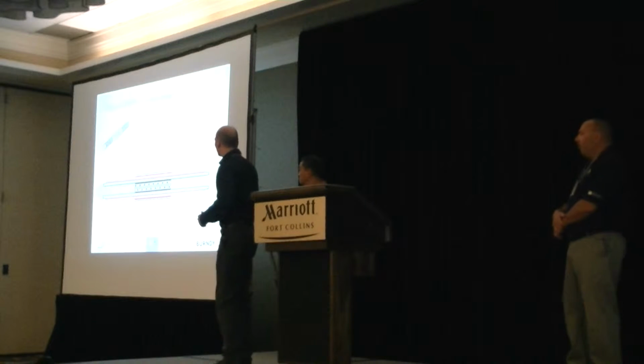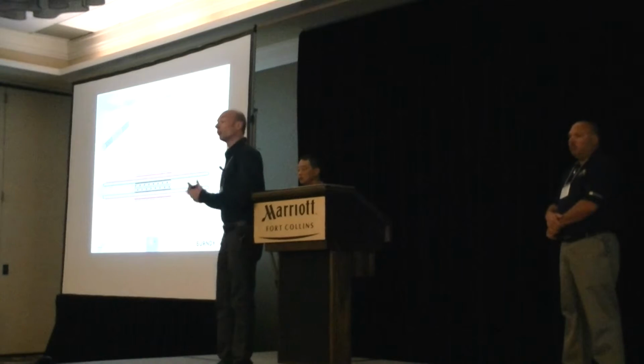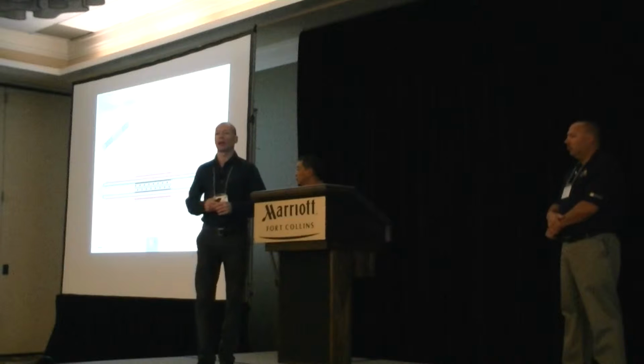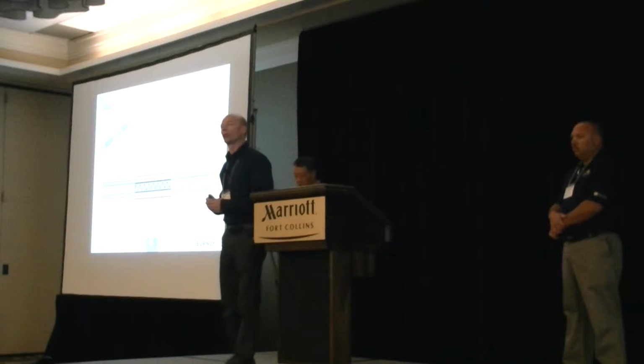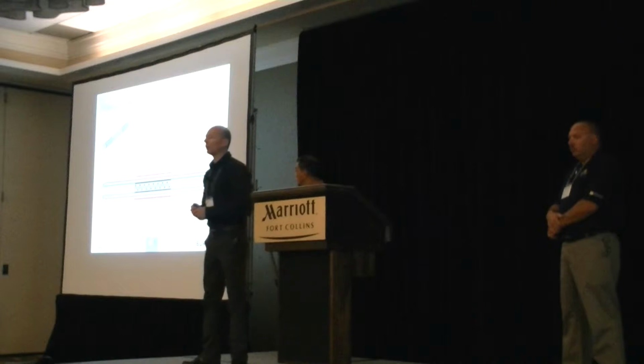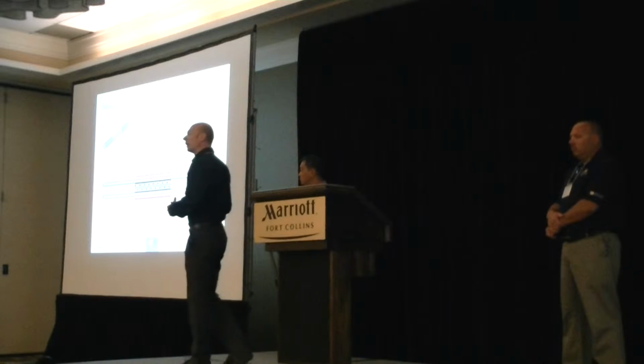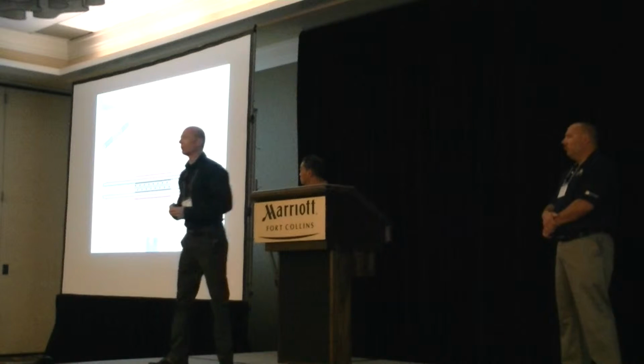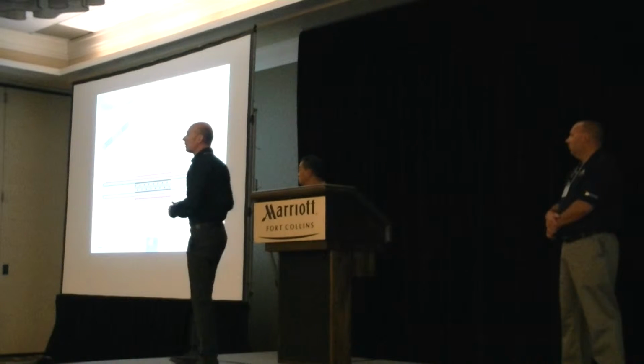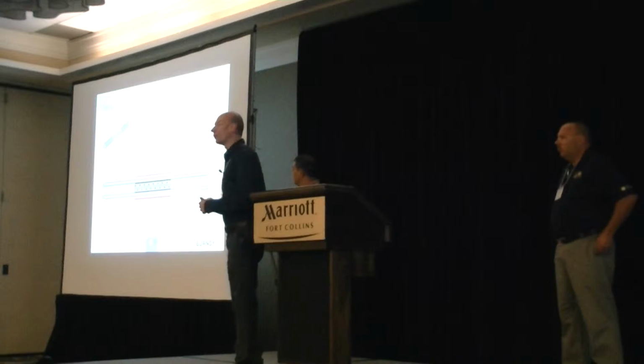The Implosive product is designed in a way that it ships with the energy, basically, in order to compress the product onto the conductor. It is a high compression process. It is not a fusing type of process that many people often associate with an Implosive product. It does have some unique design features. The materials used are substantially different than what would typically be used in a traditional tool and die type of system. And we have so much energy available to us in this wrapped formation that we're able to think outside the box, if you will, as far as what materials we use and how we go about the design process.